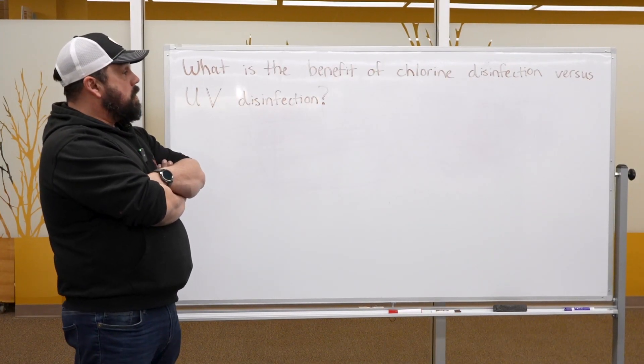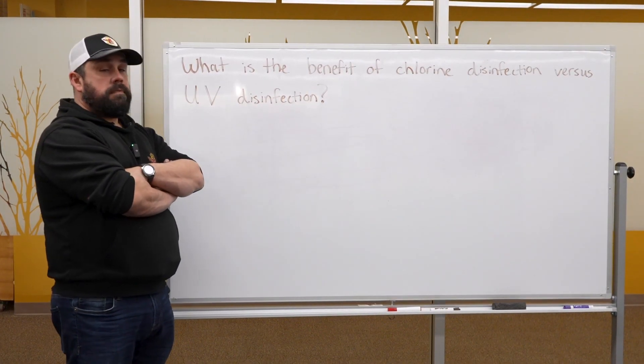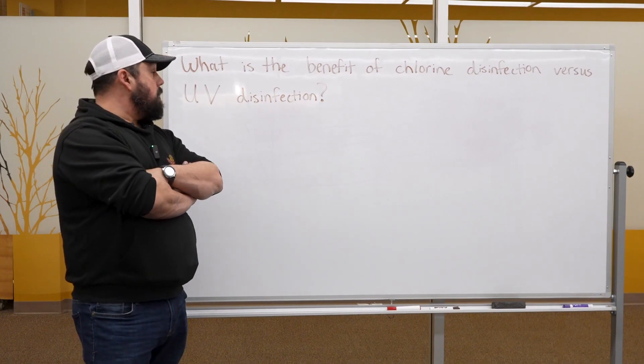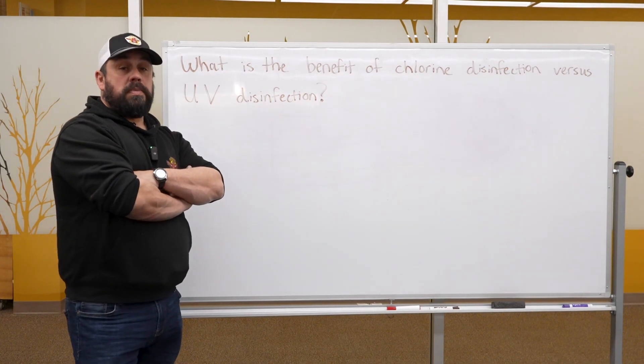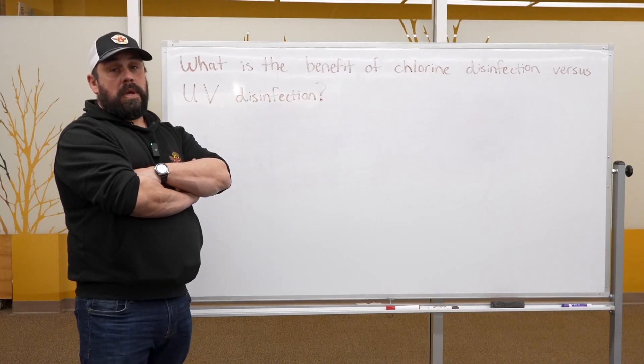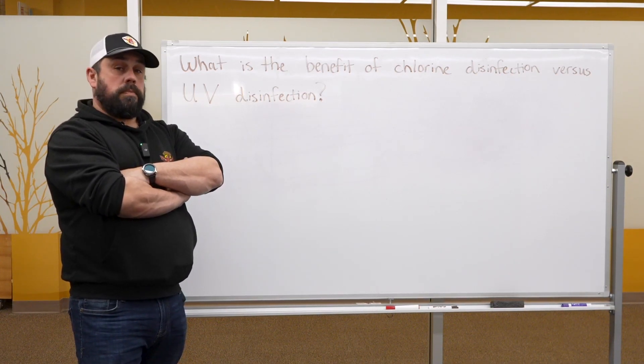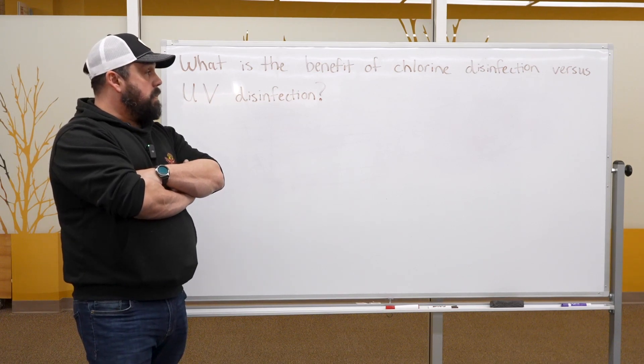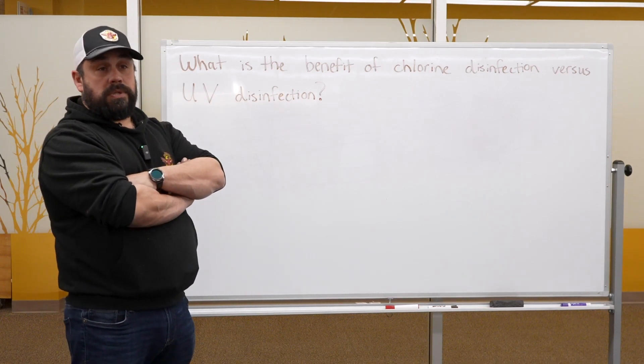What is the benefit of chlorine disinfection versus UV disinfection? Now UV disinfection is a great way to disinfect, but there is no residual treatment downstream. So if you're using only UV disinfection, you will have no protection downstream, whereas chlorine disinfection works better because there is a residual left in the water.